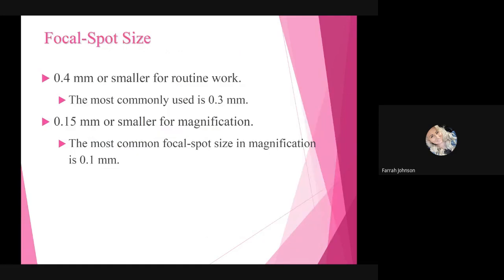So then that brings us to focal spot size. So know that 0.4 millimeters or smaller is typically used for routine work. The most commonly used is going to be 0.3 millimeters. Now, when dealing with magnification, a 0.15 millimeter or smaller can be used. However, the most common focal spot size in magnification is going to be 0.1 millimeters.